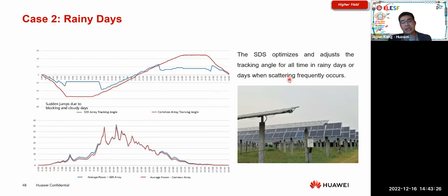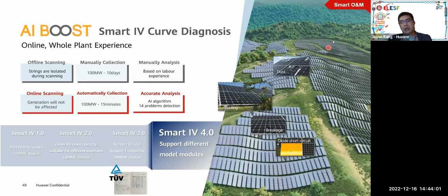This is similar to what we provide for residential and C&I inverter scenarios - the integration of IV curve technology. PV module problems are common: dust issues, shading, glass breakage, short circuits. Imagine having to scan the performance of all PV panels - I know of a 50 megawatt plant in Malaysia where it took about 3 to 4 months to manually scan all the strings.